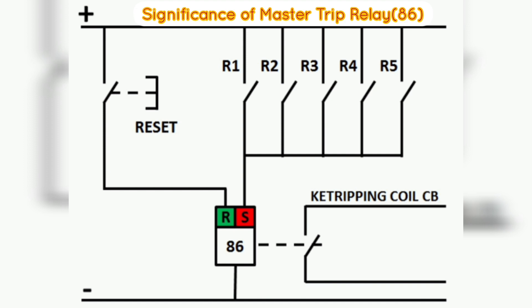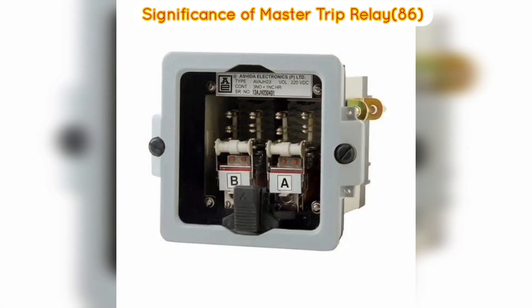Fourth, a Master Trip Relay is a high-speed auxiliary tripping relay and it immediately issues a trip command to the circuit breaker's trip coil. The operating time of the relay is 10 milliseconds nominal at rated voltage. We cannot directly wire the protection relays with a circuit breaker's trip coil, as that does not have an anti-pumping circuit. The anti-pumping circuit interrupts the tripping command once the breaker gets tripped. The Master Trip Relay releases a single pulse for tripping, and thus no anti-pumping circuit is required in the circuit breaker.